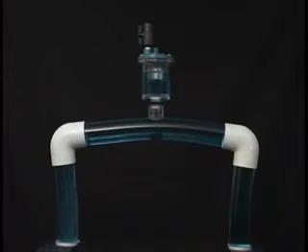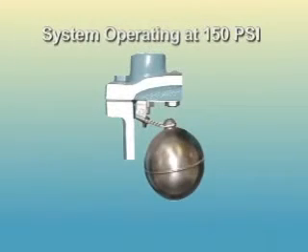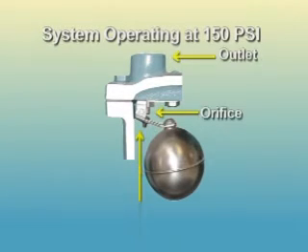An air release valve will continue to open, releasing air during system operation, because forces acting to open the valve are greater than forces acting to hold the valve closed. In the absence of water, the only force acting to hold the valve closed is the system's working pressure. This is multiplied by the total area of the valve's opening, or orifice, to atmosphere.